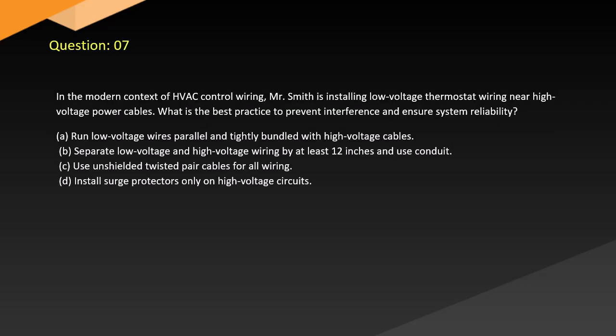Question 7. In a modern context of HVAC control wiring, Mr. Smith is installing low-voltage thermostat wiring near high-voltage power cables. What is the best practice to prevent interference and ensure system reliability? A. Run low-voltage wires parallel and tightly bundled with high-voltage cables. B. Separate low-voltage and high-voltage wiring by at least 12 inches and use conduit. C. Use unshielded twisted pair cables for all wiring. D. Install surge protectors only on high voltage circuits.